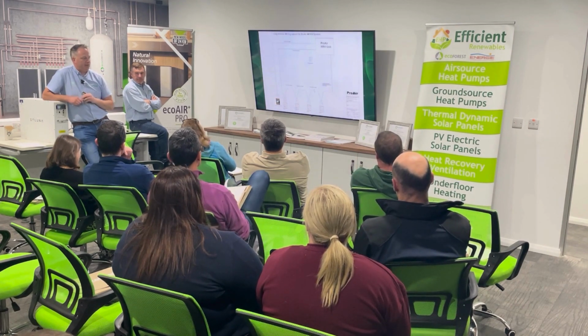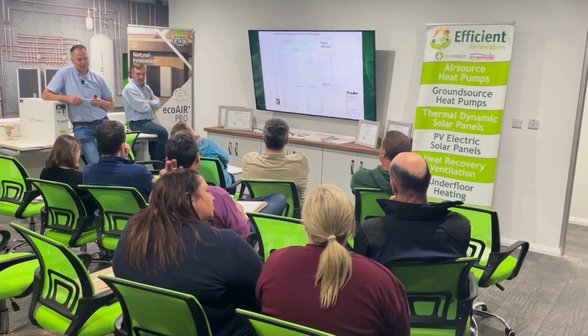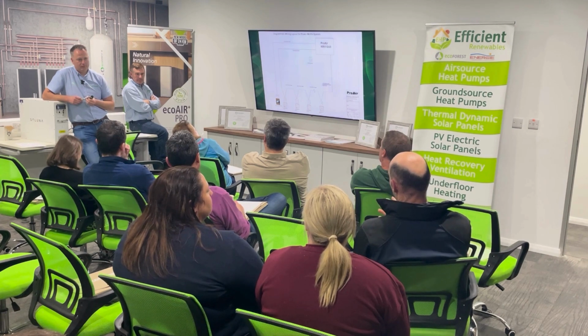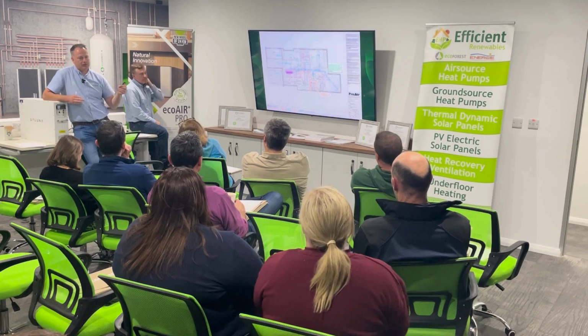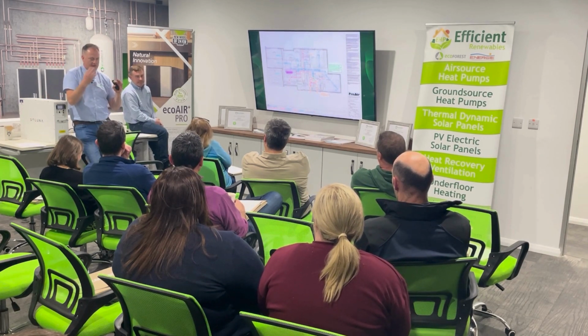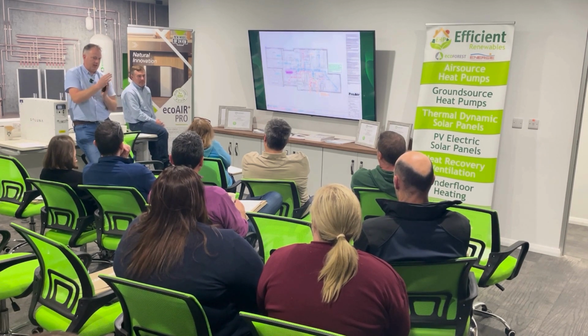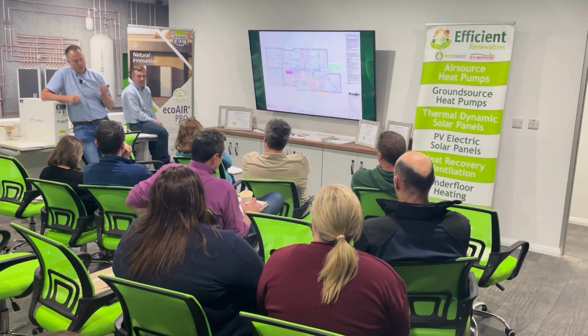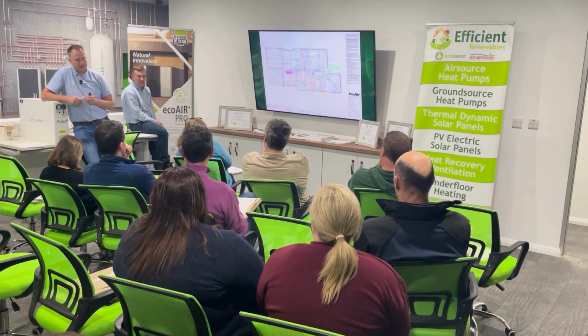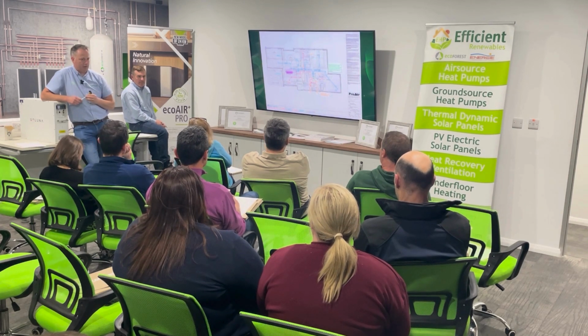Any questions on any of that on the heating side of things? Is that pure air circulation, or is there an option to actually bring the air temperature to a certain temperature to put it back into the room? Inside the unit are cross flow filters, and it's whatever temperature we take from, we'll say, the ensuite or the bathroom. It's whatever temperature that filter can cope with crossing over, and then we're putting that warm air back into the room at maybe, if we're lifting at 21, we'd like to be putting it in at 19, 20 degrees. But it's purely only a heat recovery mechanical ventilation system. There's nothing in there to take the temperature up in the ductwork.